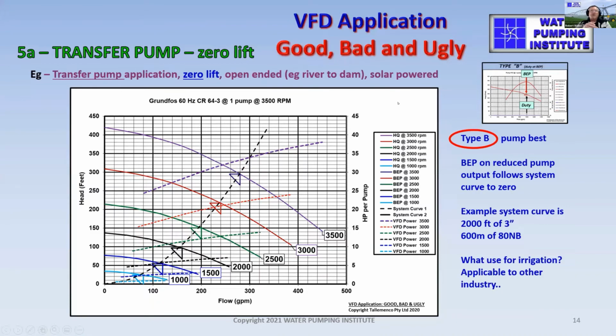Let's have a look at a transfer pump application, typically with a near zero or zero lift. And it's open-ended. It might be a transfer pump from a river to a dam with very little lift, and it might be solar powered. In this particular case, as you slow the pump down, the best efficiency point goes right off in an exponential curve back to zero. Now, if you were to plot a resistance curve or a system curve for 2,000 feet of 3-inch pipe, it will follow almost the exact trajectory of those best efficiency points.